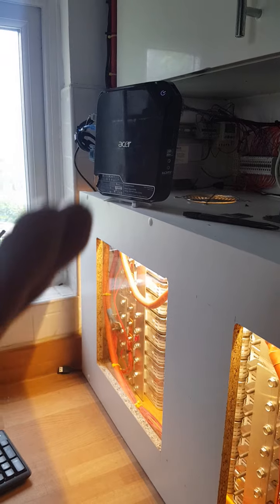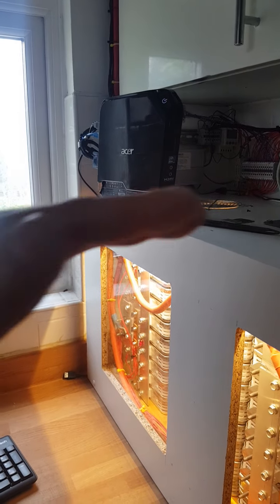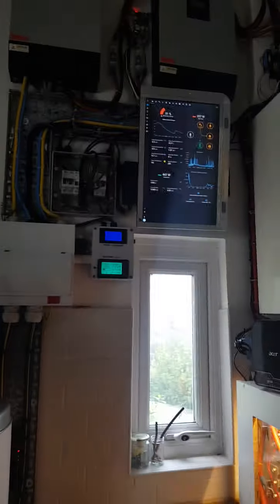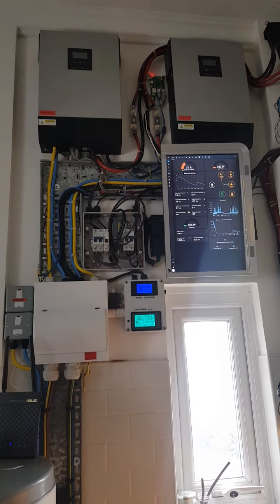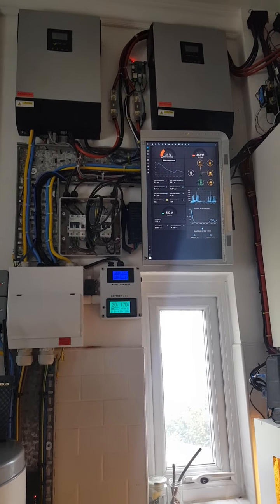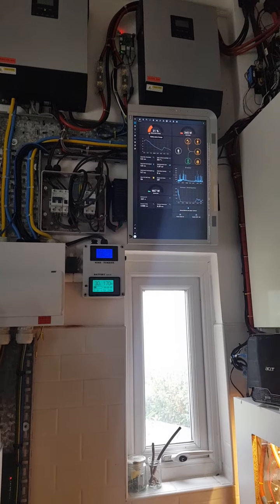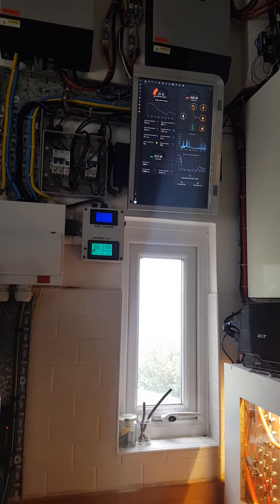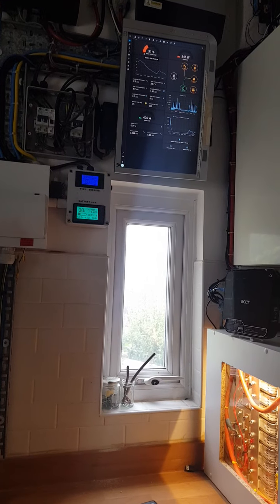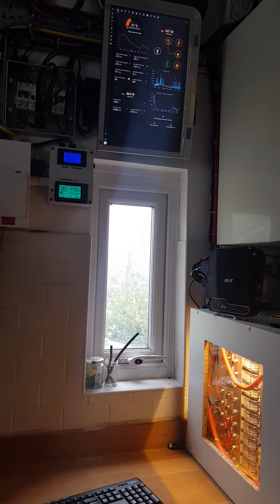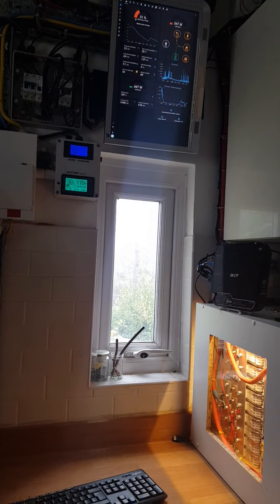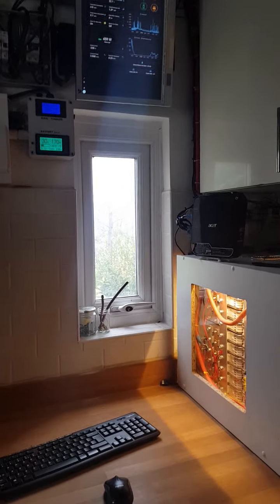The only downside is because this can't talk with the inverters, your charging curve hasn't really got a taper — well, it tapers internally, because effectively they're set up for custom batteries, in this case a modified lead acid charging algorithm almost. So bear in mind, it might whack the juice in until it gets to a certain voltage, then slowly taper off and ramp down.